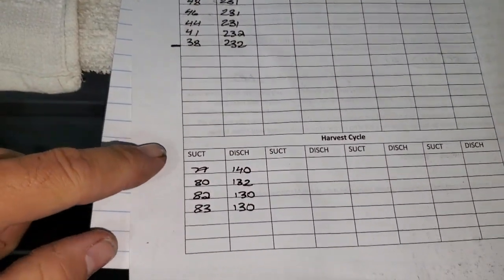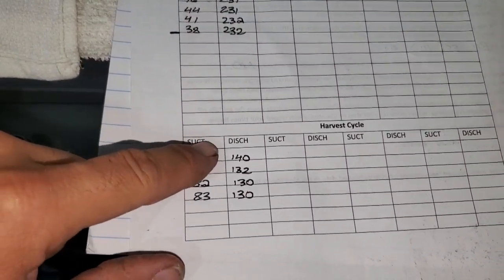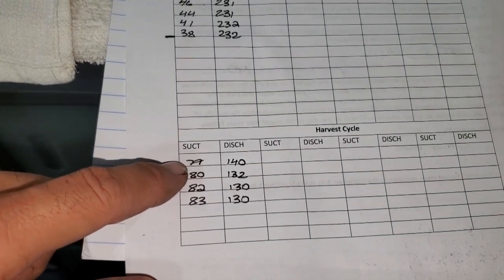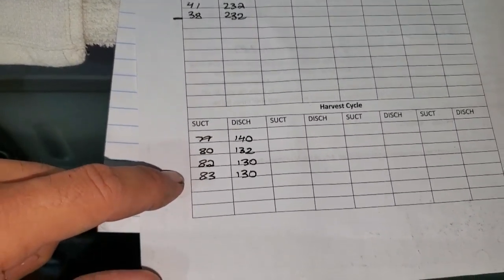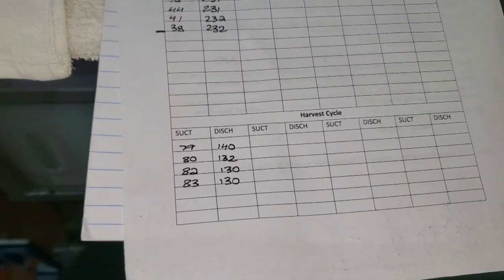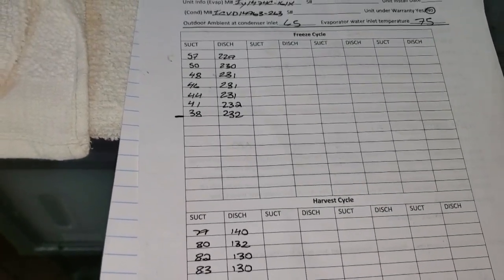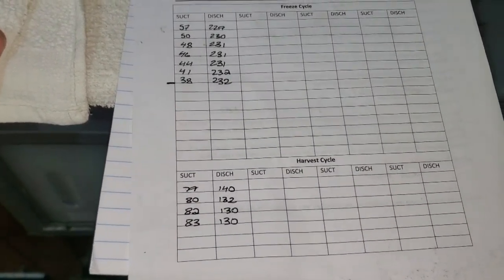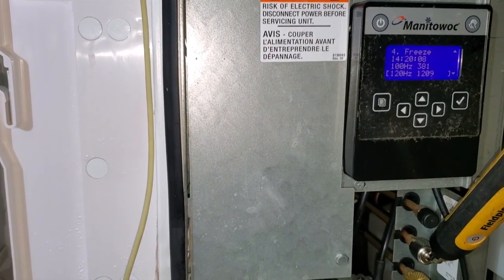This one's a little bit discomforting. Usually you just see the head pressure being low, but this one's right on the border of being low on the suction pressure too. So it's possible we could have a refrigerant charge issue. But like I said, I'm just going to let the customer keep an eye on it, and we'll see what we can do.